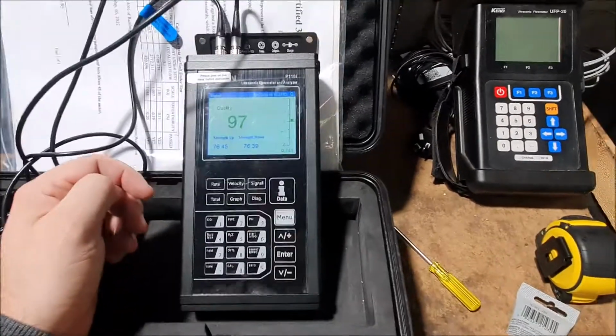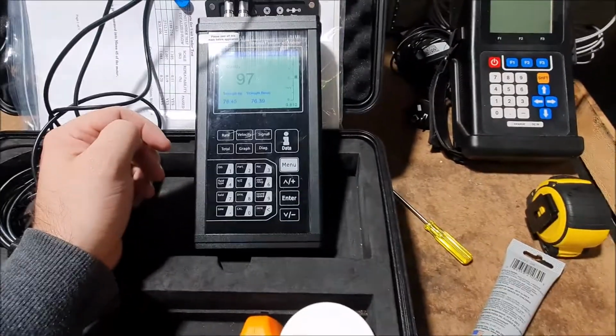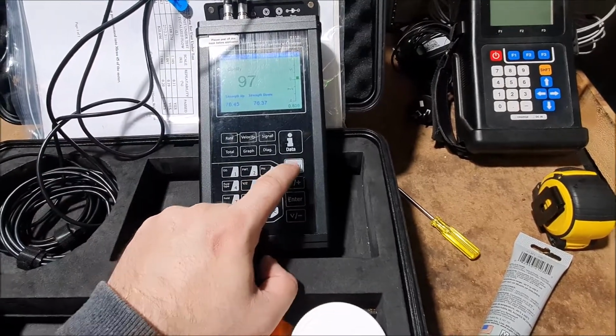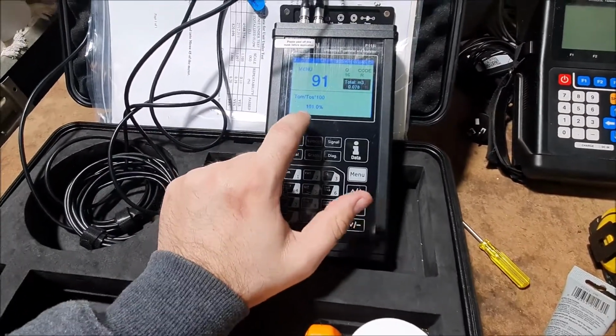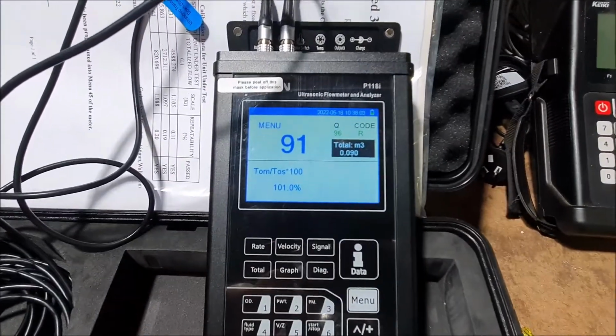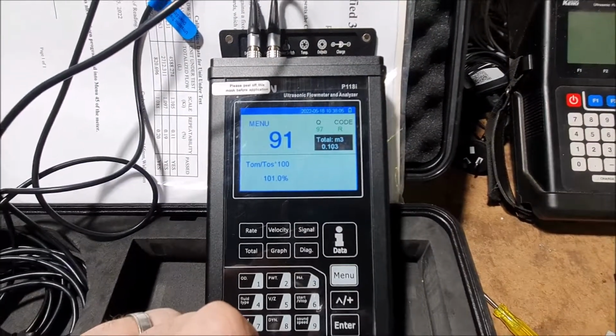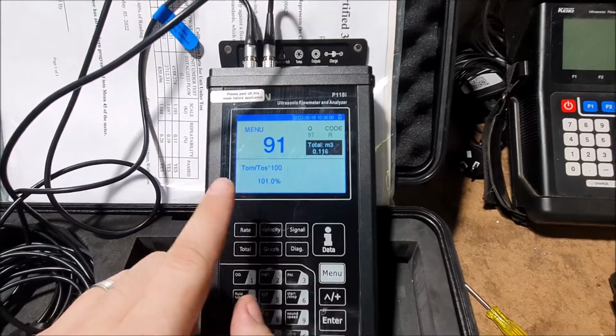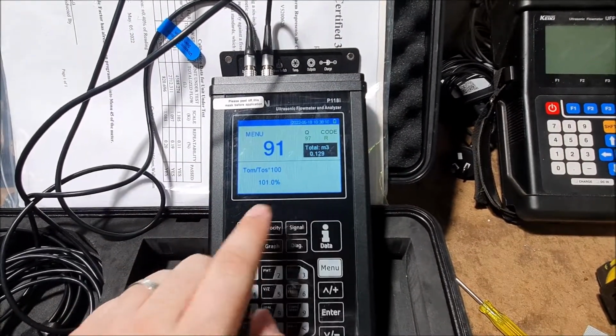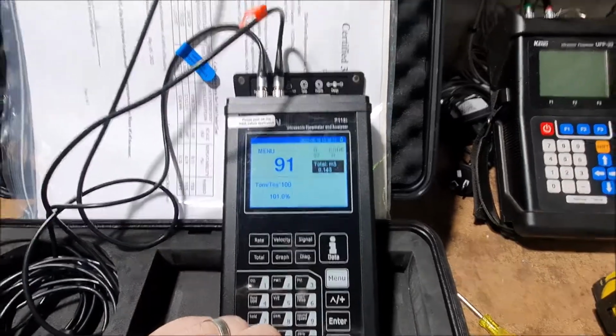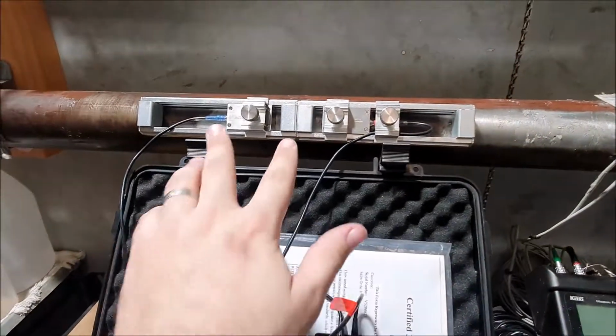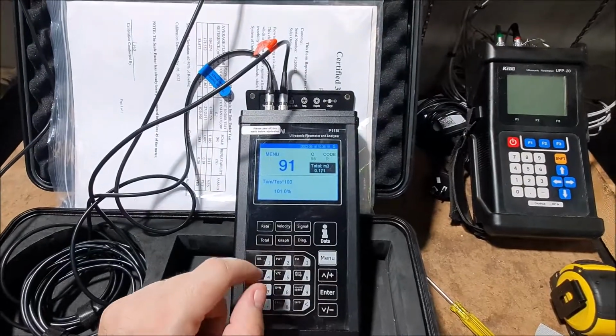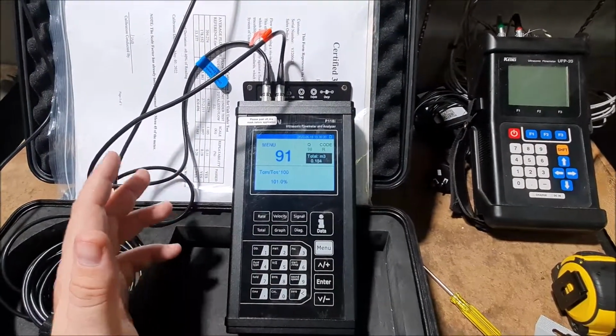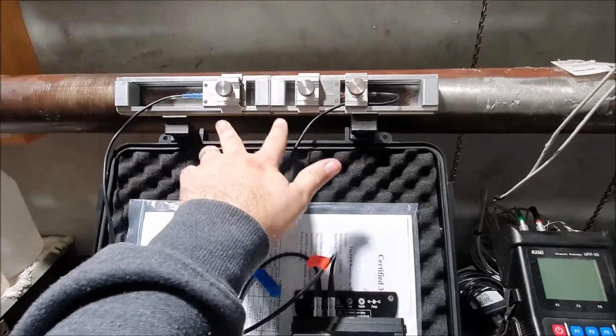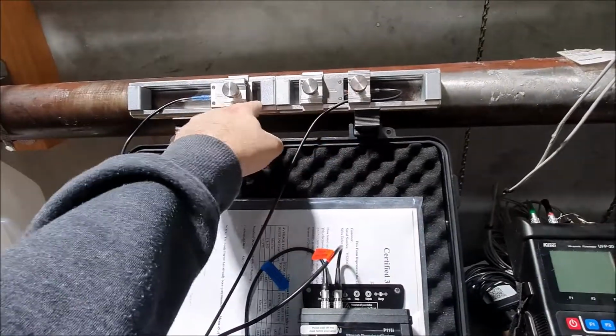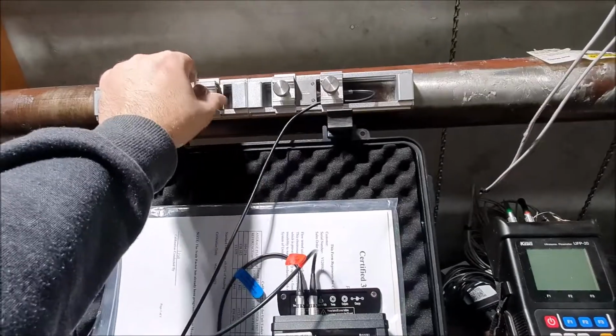I'm happy with that. And then one other value we want to look at is on menu 91. That's this percentage value. This you want within 3% of 100, so it can be in the range of 97 to 103. We're at 101, so I'm happy with that. Usually if that's out of spec, it'll be that either a parameter is wrong, maybe your wall thickness you've entered incorrectly or something like that. It's basically telling you a ratio, so maybe your transducers are in the wrong position or something like that.